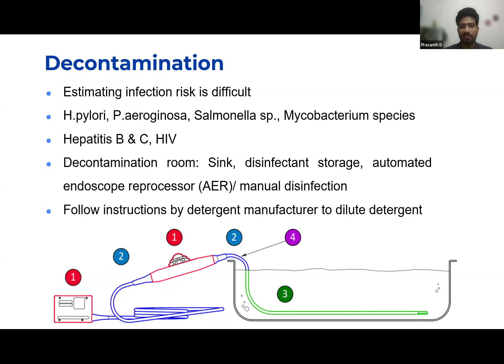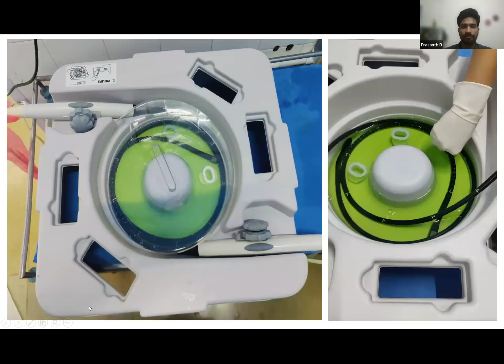The decontamination room should be separate, and it should have a sink area, disinfectant storage, and either an automated endoscopic reprocessor or manual disinfection. Always follow the instructions of the detergent manufacturer to dilute the detergent. Here we can see only the labeled three. The tip and flexible shaft should be immersed into the high level disinfectant, not the control housing, the cable or the connector. This is what we are using in our institute. This is the manual disinfection.